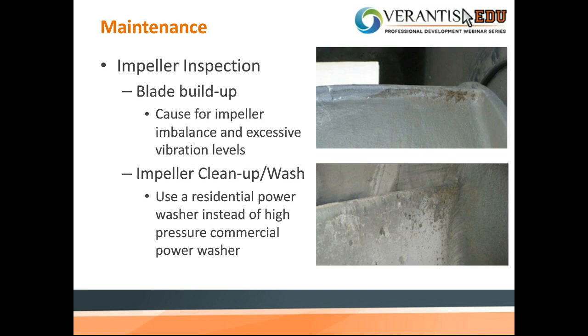So it's wise to inspect the impeller, like I said, during routine maintenance or when the fan is off. So we have seen blade buildup. If you have a particulate environment, buildup can happen on the blade. And what happens is that there's an imbalance, and excessive vibration levels can happen, causing havoc on the fan. You can clean this though.